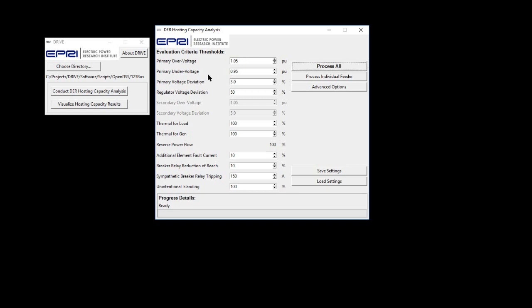This is why undervoltage has an evaluation threshold as well as thermal issues due to additional load. The hosting capacity will be determined for each issue regardless of whether the issue will be considered as a potential constraint. The decision about which issues to include in the final hosting capacity assessment is made when viewing the results.